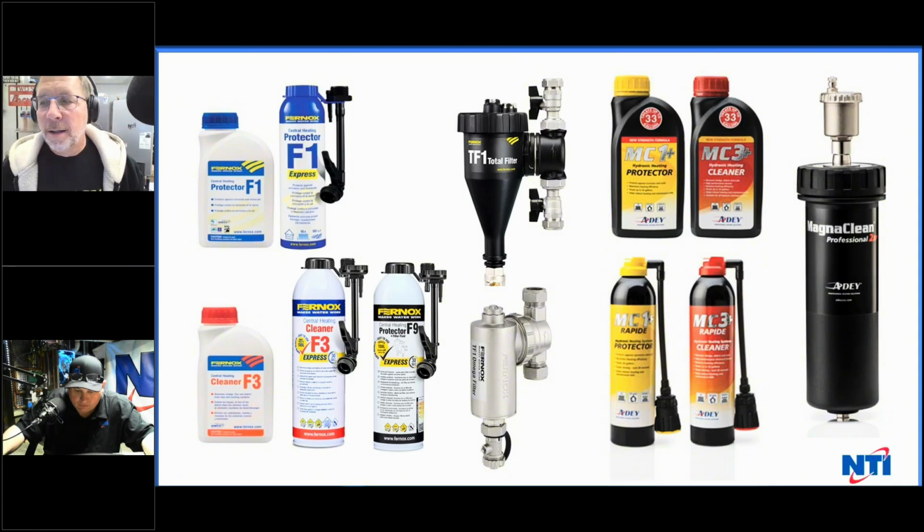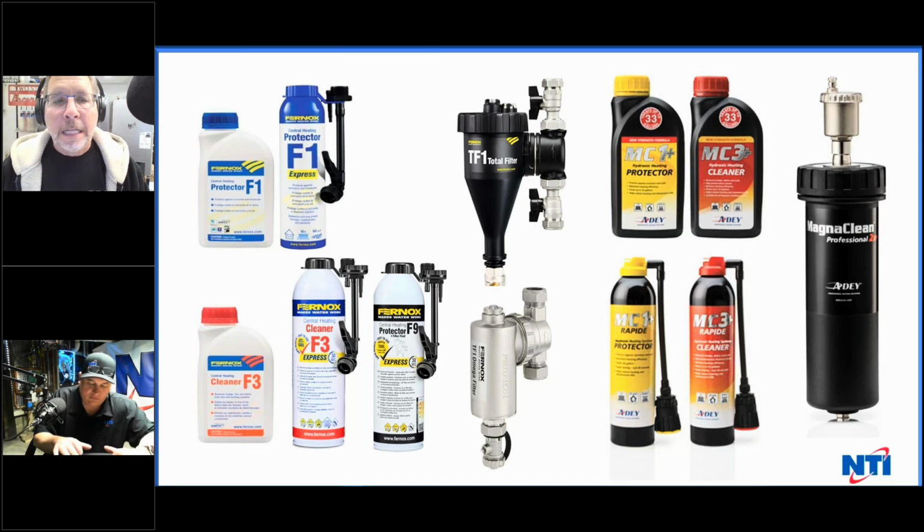All right, so you put in the F3 product if you have an existing boiler there. You put it in there for 4 hours if you have heat. If you don't have heat, say it's summertime where the burner's out, put it in there for 4 days with circulation. Clean it and flush it out after, or within 14 days. No more, because after 14 days, everything starts to settle out.